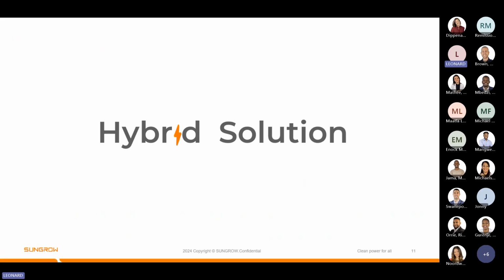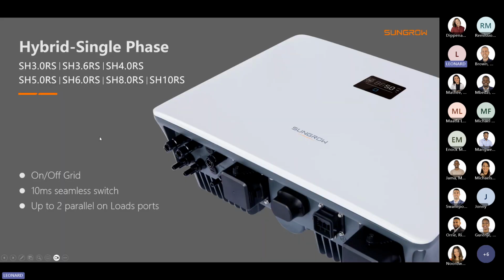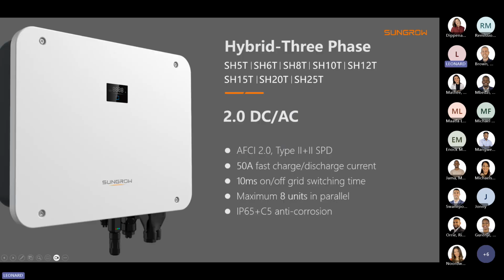Then in terms of hybrid solutions, for our region, we have the 6RS and the 10RS single phase solution. This is an on-off grid solution with the black start capability. It has a 10 millisecond seamless changeover, and you can parallel up to 2 units of these inverters. Then just in terms of hybrid 3-phase, so currently for our region, we have the 15T and 25T, which is a 15 kilowatt inverter and 25 kilowatt inverter.